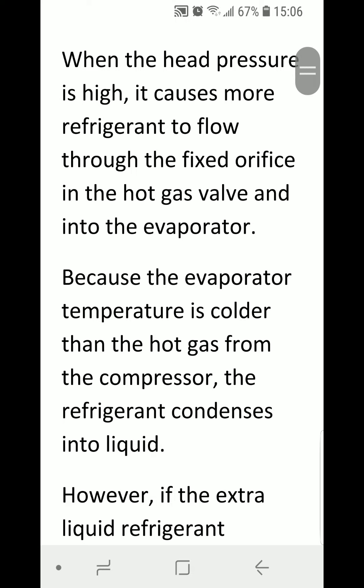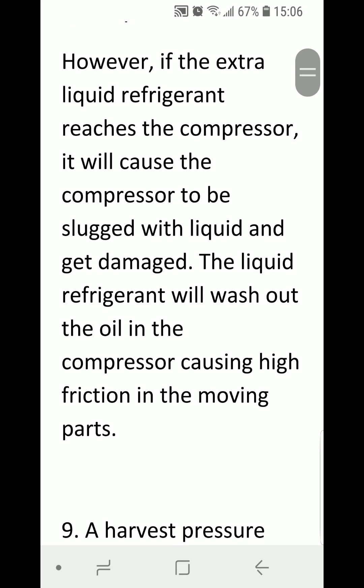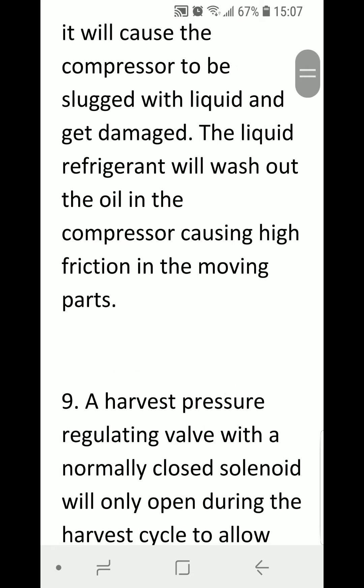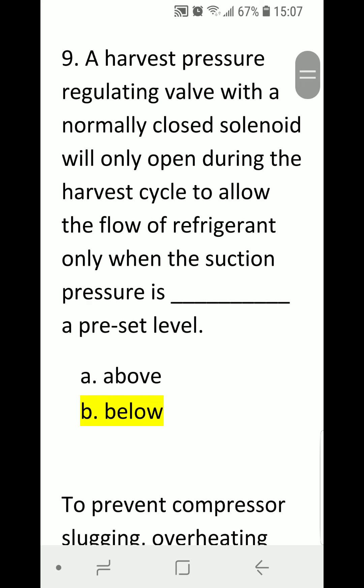When the head pressure is high, it causes more refrigerant to flow through the fixed orifice in the hot gas valve and into the evaporator. Because the evaporator temperature is colder than the hot gas from the compressor, the refrigerant condenses into liquid. If this extra liquid refrigerant reaches the compressor, it will cause slugging and damage the compressor by washing out the oil, causing high friction in the moving parts.